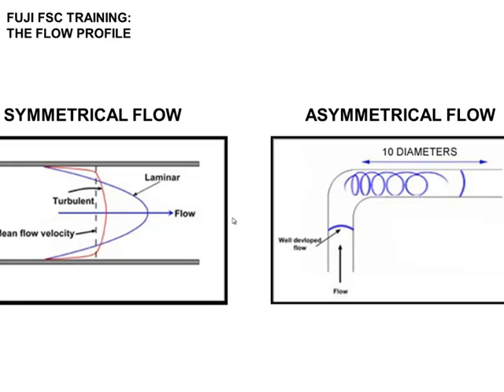Lower flow rates, less straight run of pipe. Bigger obstructions at an elbow, more straight run of pipe. The picture to the right is referred to as an asymmetrical flow profile. In this case, I have my flow going up this 90-degree elbow. Shorter distance, longer distance, guess what? I get a tumbling effect after this elbow here.